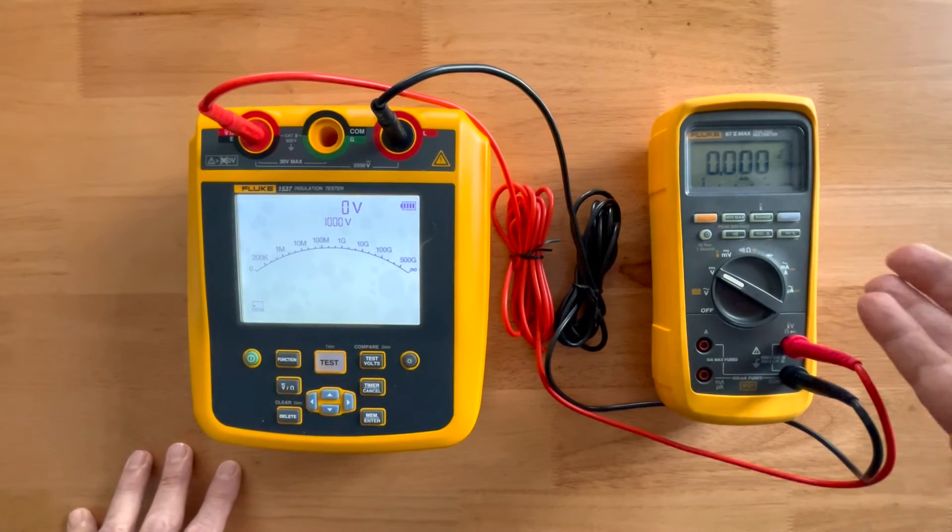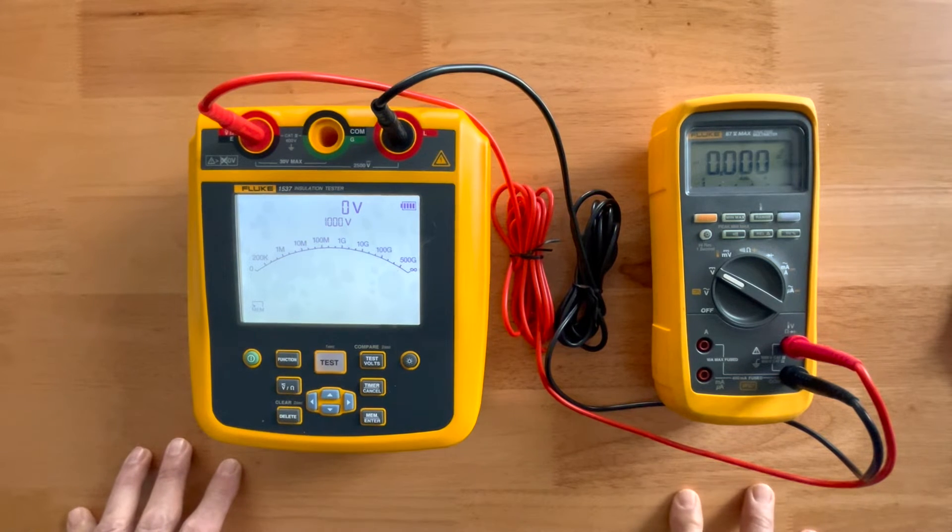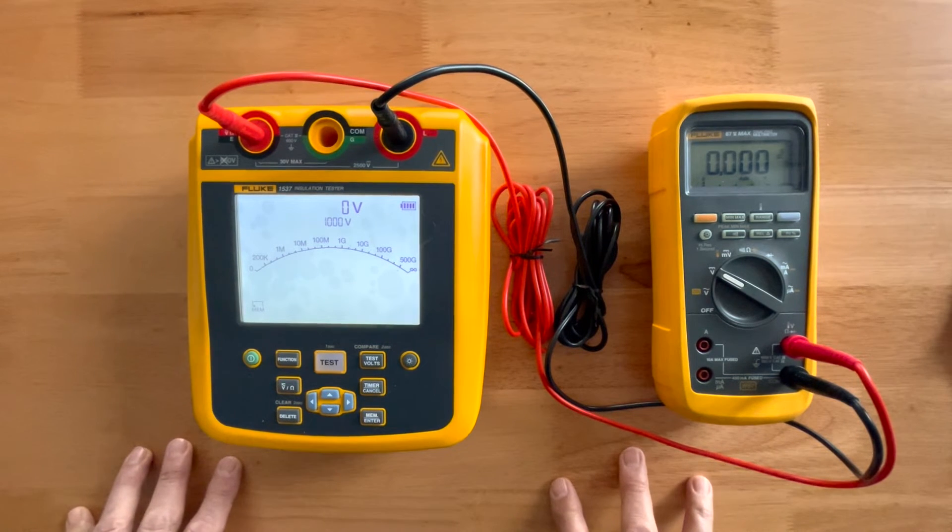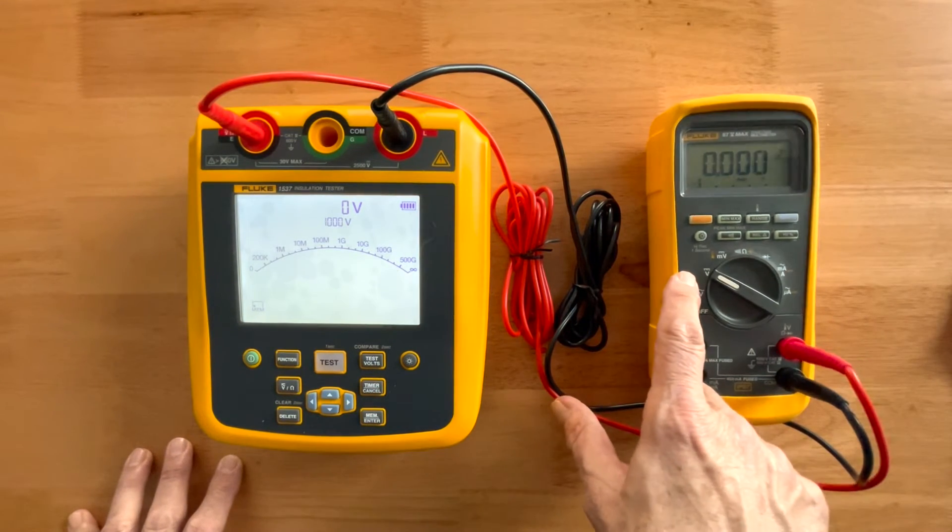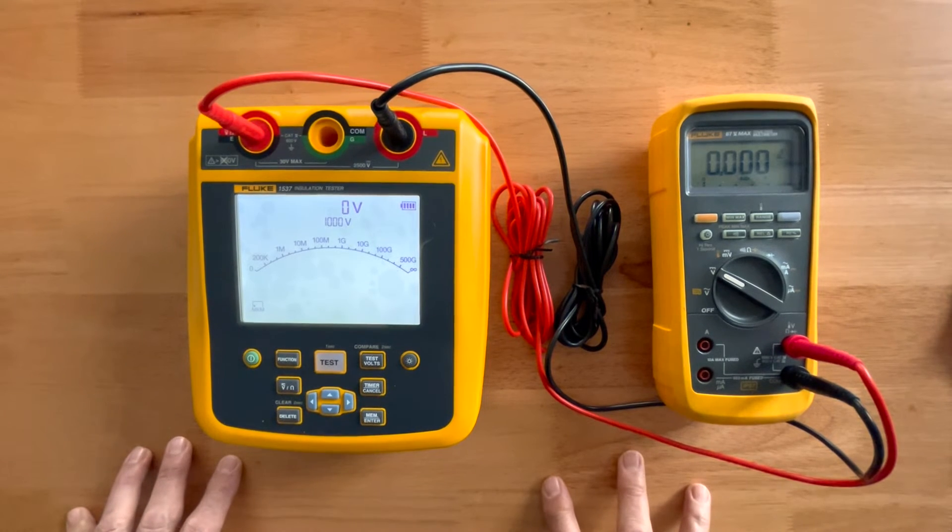And off to the right here, you may or may not recognize this device, probably the most popular meter we sell in the entire world, called an 87V. And I have this flipped to volts DC, with it connected to the output side of this insulation tester. And I'm going to start the test.